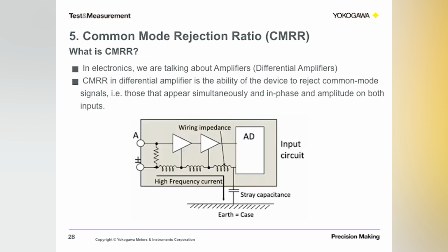So, that was the one factor that contributes towards the uncertainty. Let's look at another factor: common mode rejection ratio. Apart from just internal phase shifts between voltage and current, you also have to be cognizant of another specification called CMRR, commonly known as common mode rejection ratio. In electronics, when we are talking about CMRR, we're mainly talking about amplifiers or differential amplifiers, so to speak.